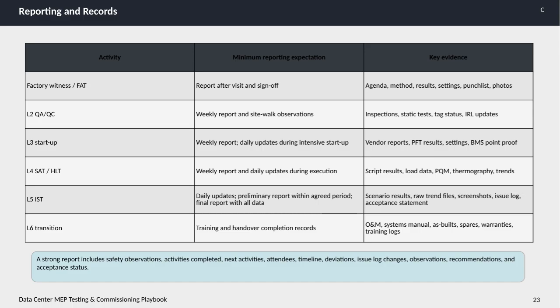For Level 3 startup, there's an increase in reporting frequency. Weekly reports are mandatory, with daily updates during intensive startup phases. Key evidence here includes vendor reports, performance functional test results, settings, and proof of BMS points, all critical to verifying operational readiness. At Level 4 SAT and HLT stages, weekly reports continue with daily updates during execution.